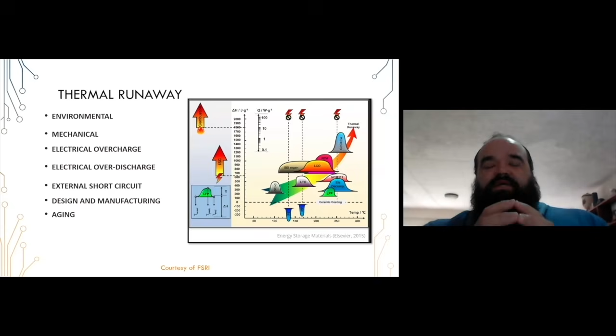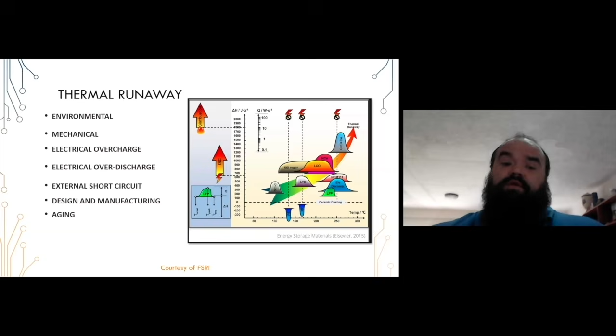Aging of the batteries is going to become more common, and I foresee a few more fires in our industry coming up. When lithium batteries reach around the 5-year mark, the chemical composition starts degrading, and it becomes more volatile. If you haven't maintained it correctly, given the aging and volatility of the battery's makeup, you could wear through that crystal lattice, the graphite barrier might be gone, and you run more of a risk with an older battery to enter thermal runaway.